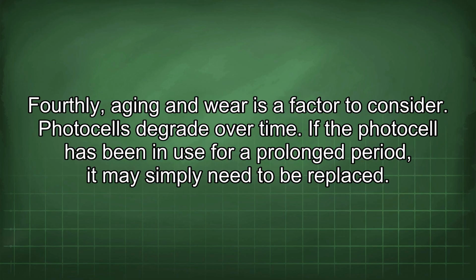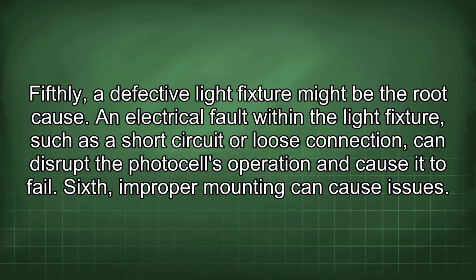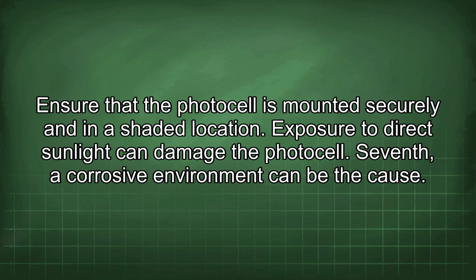Fourthly, aging and wear is a factor to consider. Photocells degrade over time. If the photocell has been in use for a prolonged period, it may simply need to be replaced. Fifthly, a defective light fixture might be the root cause. An electrical fault within the light fixture, such as a short circuit or loose connection, can disrupt the photocell's operation and cause it to fail. Sixth, improper mounting can cause issues. Ensure that the photocell is mounted securely and in a shaded location. Exposure to direct sunlight can damage the photocell.